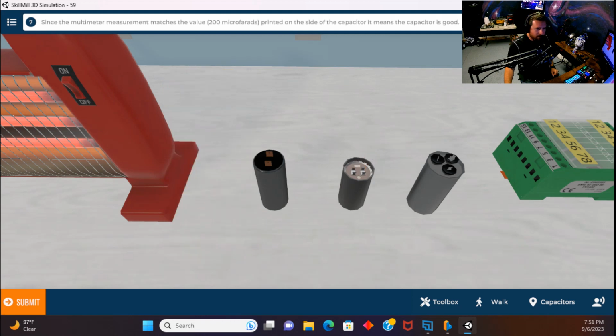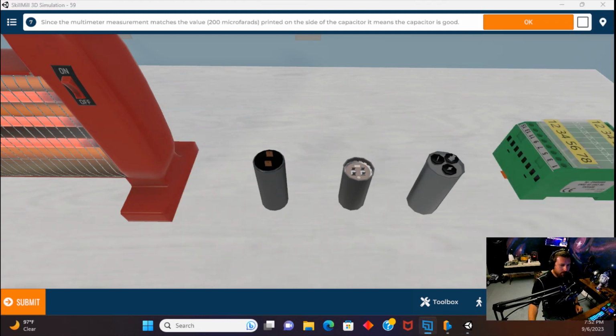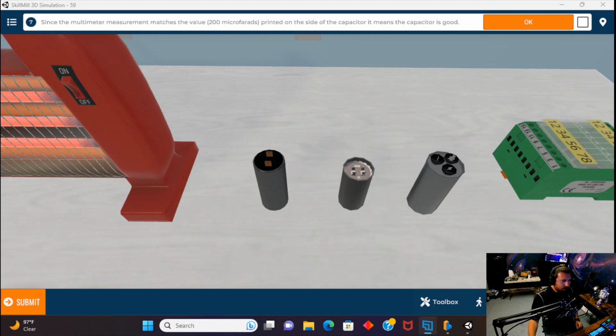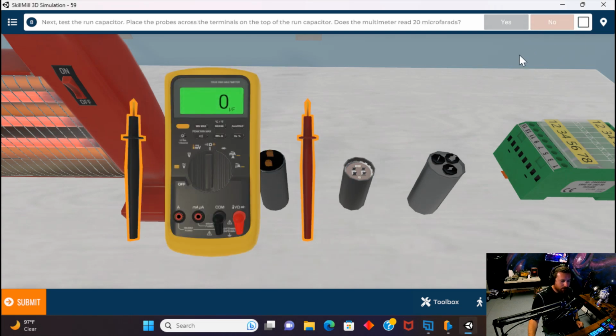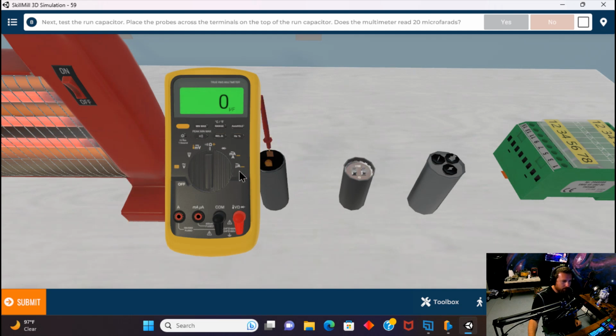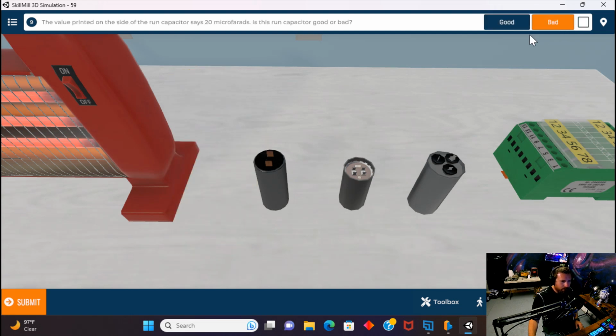Sure, we hit yes. Let me move this down here so you guys can see. Since the multimeter measurement matches the value, 200 microfarads, printed on the side of the capacitor, it means the capacitor is good. Awesome. Okay. So next, test the run capacitor. Place probes across the terminals on the top of the run capacitor. Does the multimeter read 20 microfarads? Let's put the red on the red and the black over here. Does it read 20 microfarads? Nope. The value printed on the side of the run capacitor is 20 microfarads. Is this run capacitor good or bad? It's bad. So let's get rid of it.